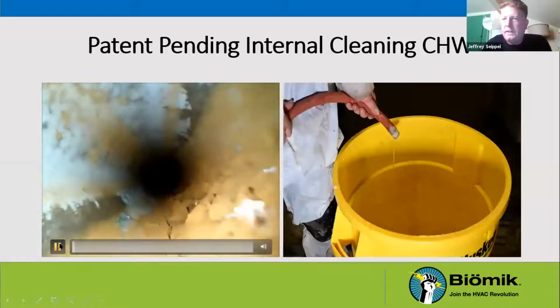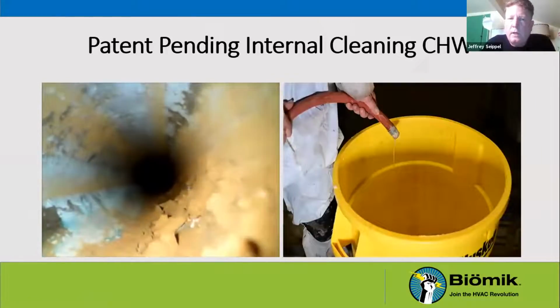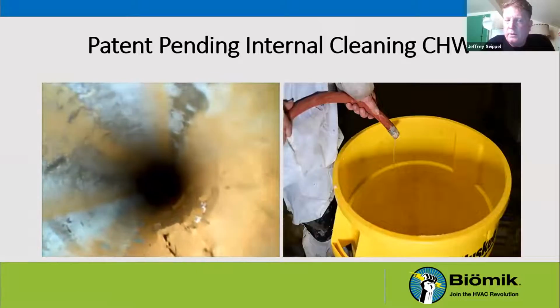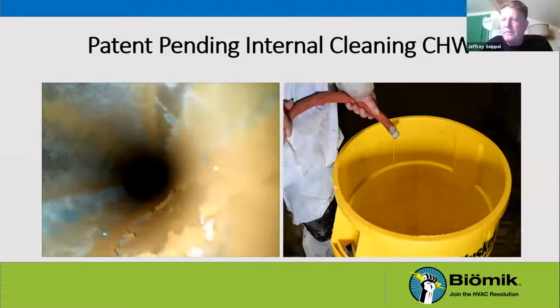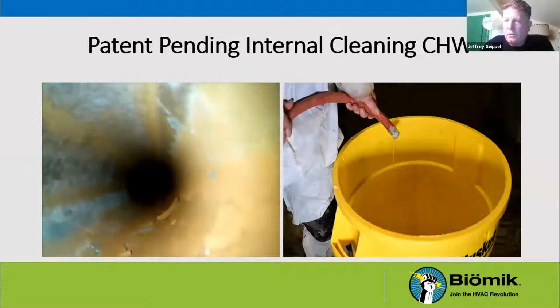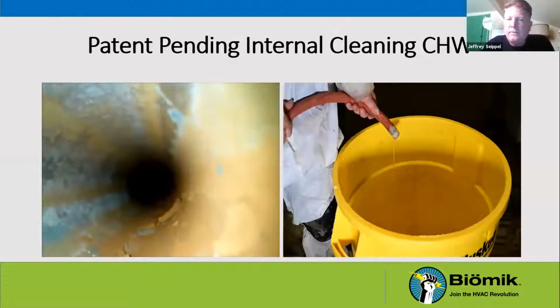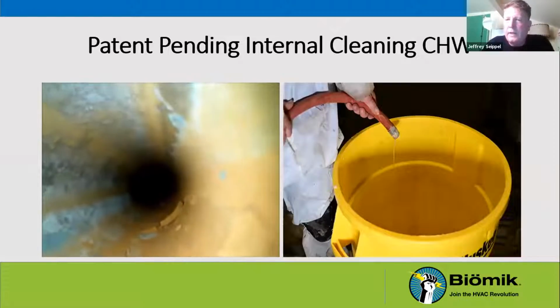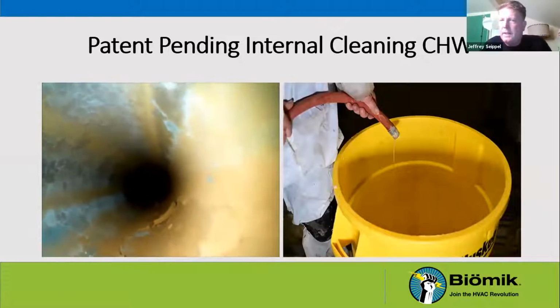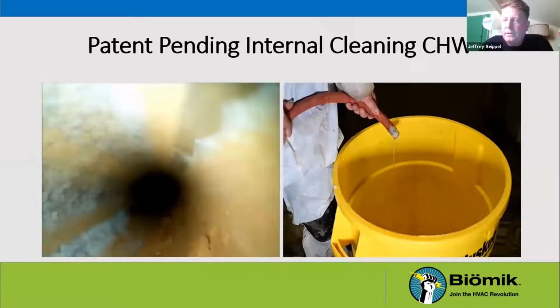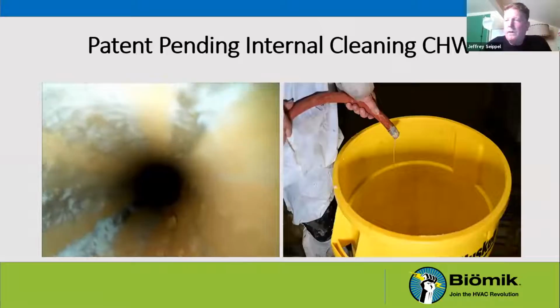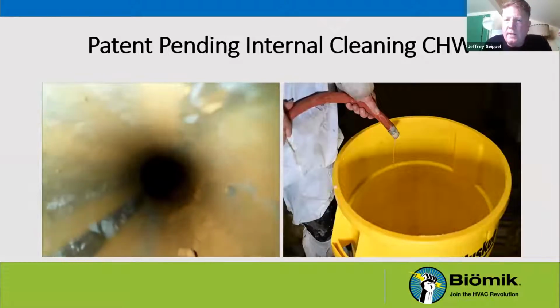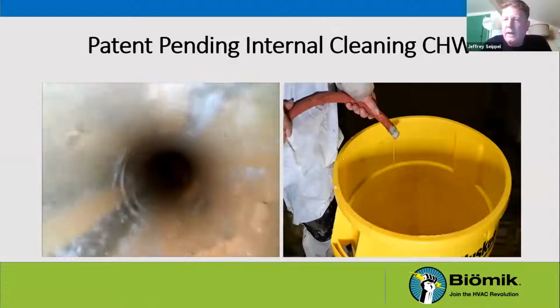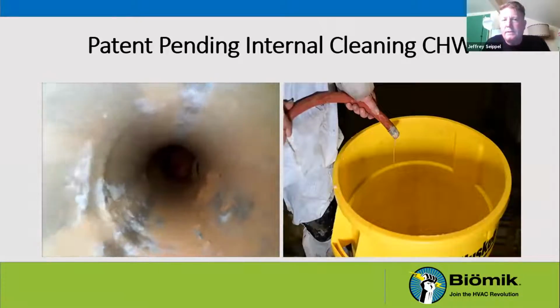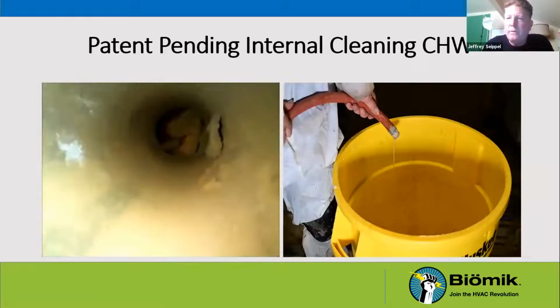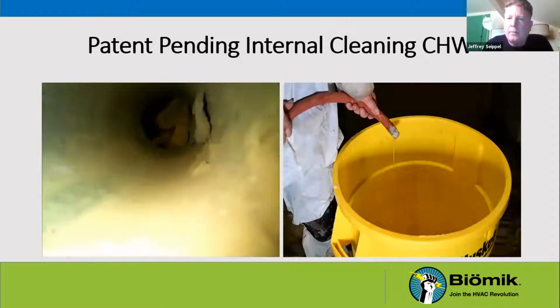So this is the inside of one of those tubes. This was taken from the old Pontchartrain Hotel. The coil was only 5 years old. We had to cross-section the coil to be able to get at it and take this video. But what you're looking at is mineral scale in the form of iron scale that builds up in all chilled water coils. The mineral scale has a very direct link to biofilm. They go hand in hand, and the biofilm actually creates the situation where the films can attach to the copper.